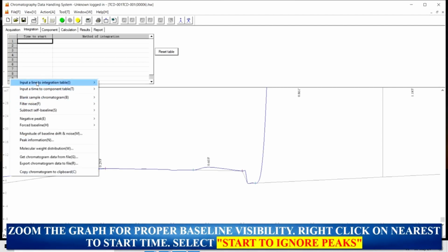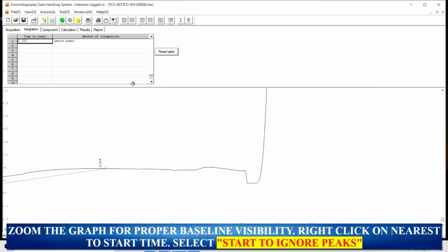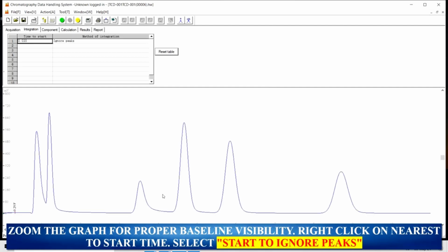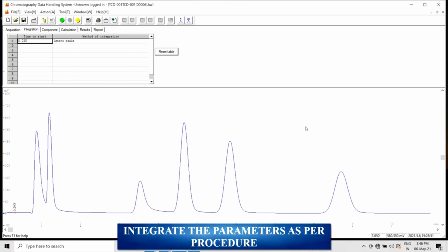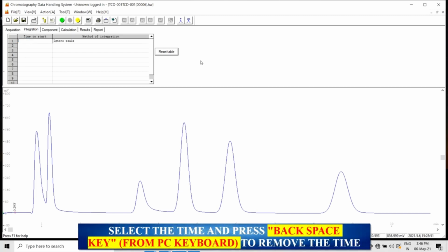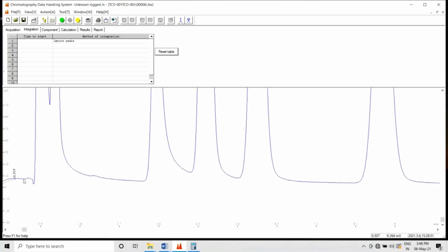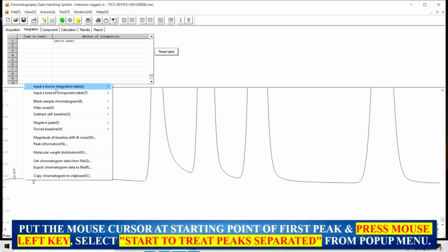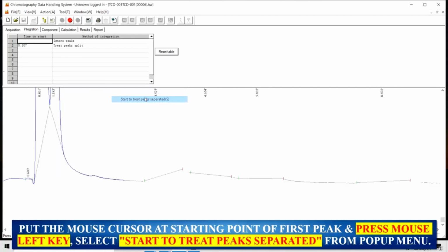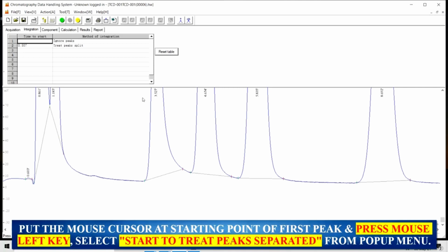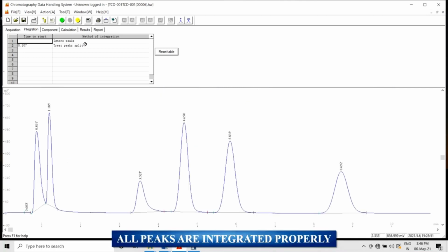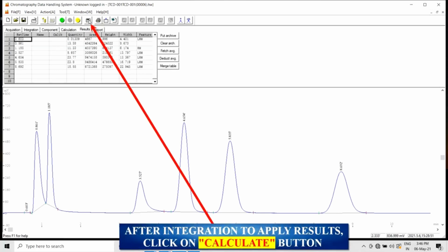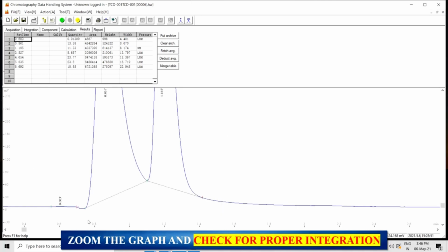Right-click on Nearest to Start Time. Select Start to ignore peaks. All peaks will be ignored. Integrate the parameters as per procedure. Select the time and press the backspace key on the PC keyboard to remove the time. Zoom the graph again. Put the mouse cursor at the starting point of the first peak and press the mouse left key. Then select the Start to treat peaks separated option from the pop-up menu. All peaks are integrated properly. After integration, to apply results, click on the Calculate button. Zoom the graph 3 or 4 times, and check for proper integration.